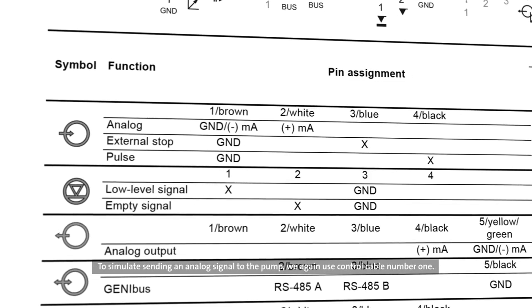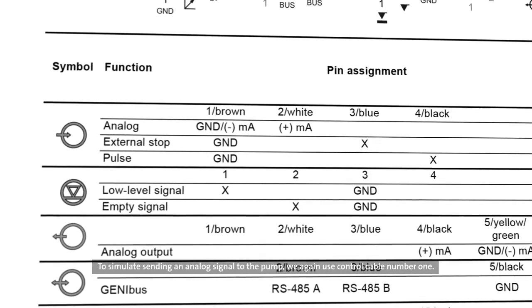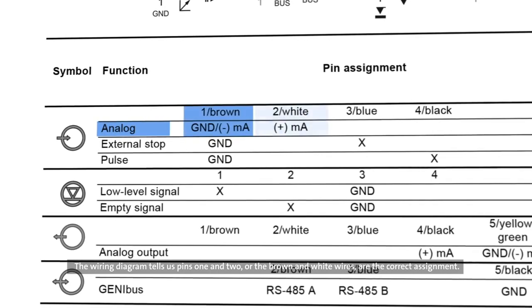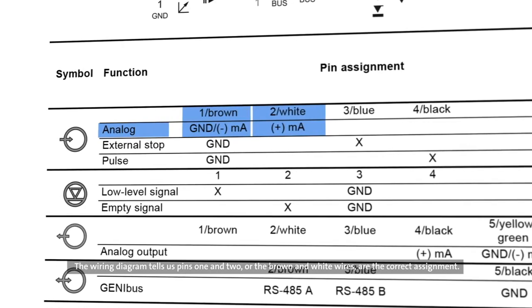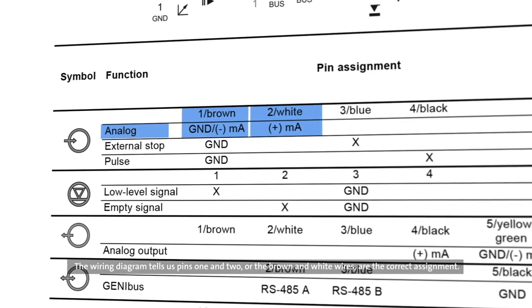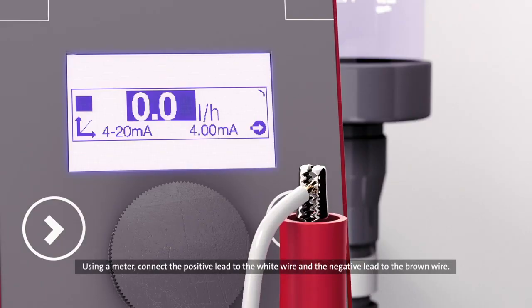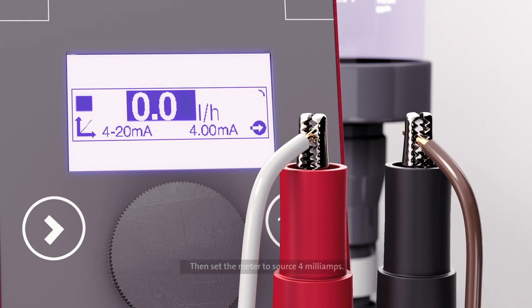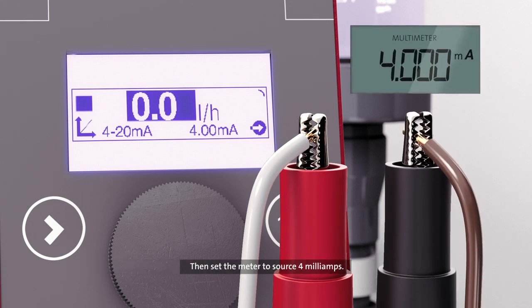To simulate sending an analog signal to the pump, we again use control cable number 1. The wiring diagram tells us pins 1 and 2, or the brown and white wires, are the correct assignment. Using a meter, connect the positive lead to the white wire and the negative lead to the brown wire. Then set the meter to source 4 milliamps. The control cube displays that the current signal is 4 milliamps.